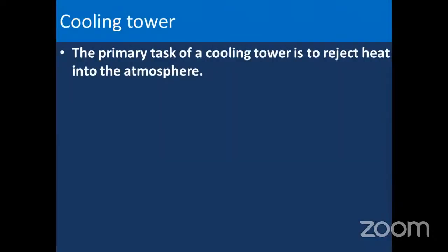The primary task of a cooling tower is to reject heat into the atmosphere. What is that major heat? The major heat is the latent heat contained in the steam. It is not the sensible heat, it is the latent heat. That's why we need such an enormous quantity of water. The heat rejected is very high, but the temperature is very low. That's why we cannot use the heat for useful purposes. In some countries, the heat is utilized for supplying hot water to homes in nearby towns. But we don't require hot water, and we cannot use that.